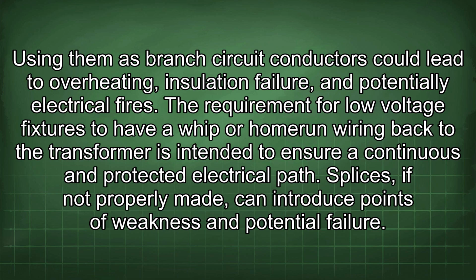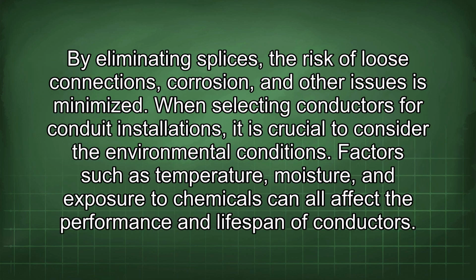The requirement for low voltage fixtures to have a whip or home run wiring back to the transformer is intended to ensure a continuous and protected electrical path. Splices, if not properly made, can introduce points of weakness and potential failure. By eliminating splices, the risk of loose connections, corrosion, and other issues is minimized.